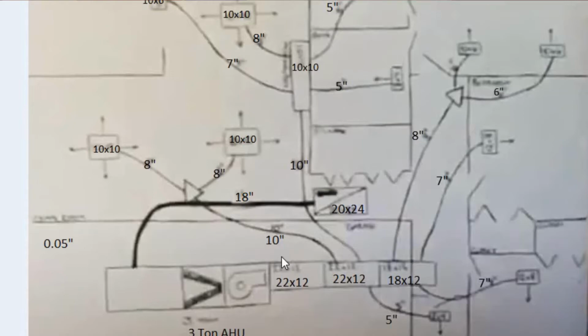Very first thing we've got to do is give us a rough layout of where our ductwork is physically able to run, and then we need to figure out where our critical paths are, our critical supply and our critical return. Now on this particular model, my critical supply, the longest run from the face of that blower, so from that blower, what is the longest run that air has to travel? It is probably either this far master bedroom or this right here, this kitchen. Okay, this 10x6 on this kitchen. So that's for our supply.